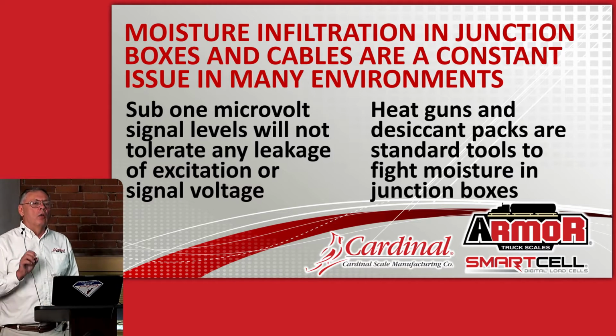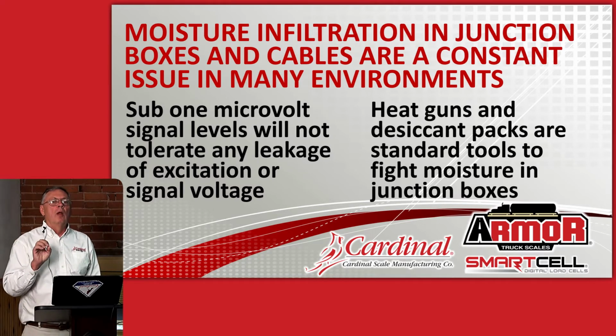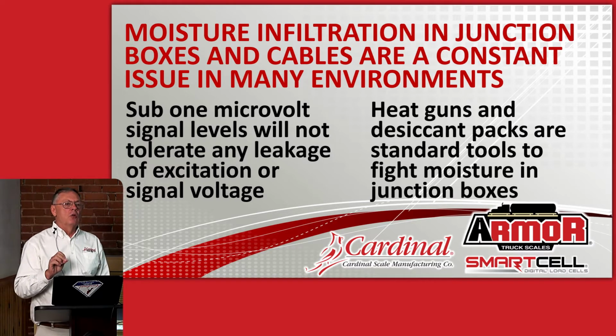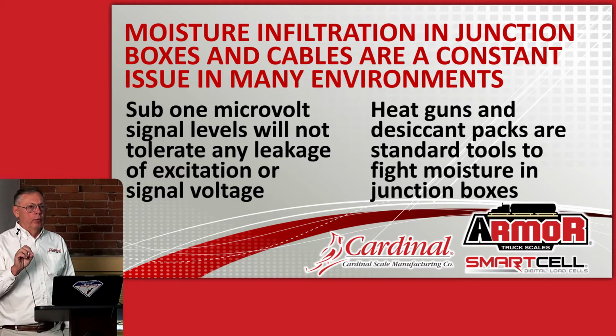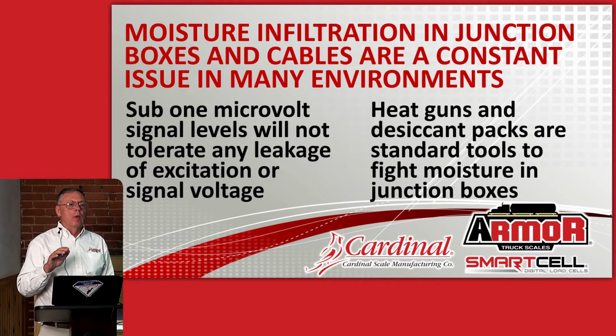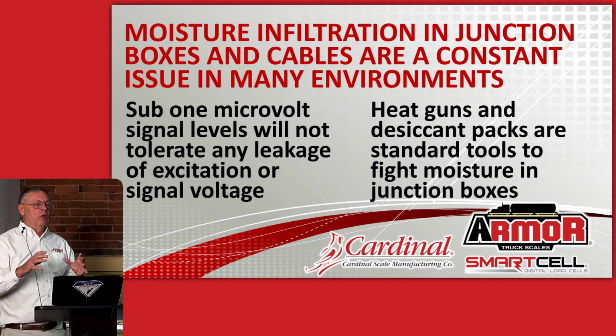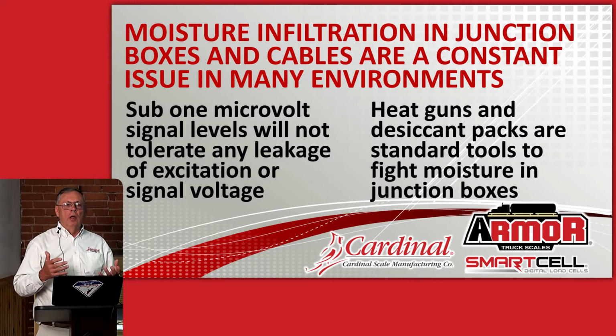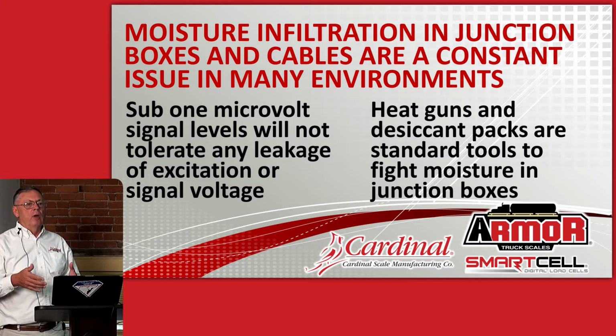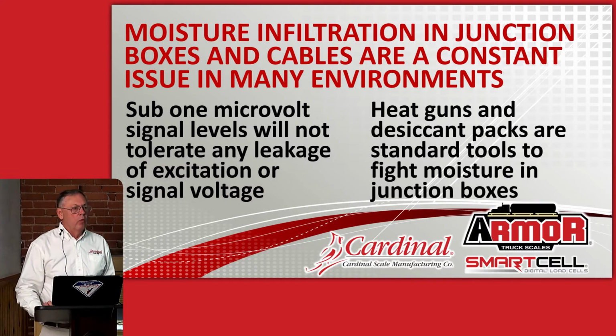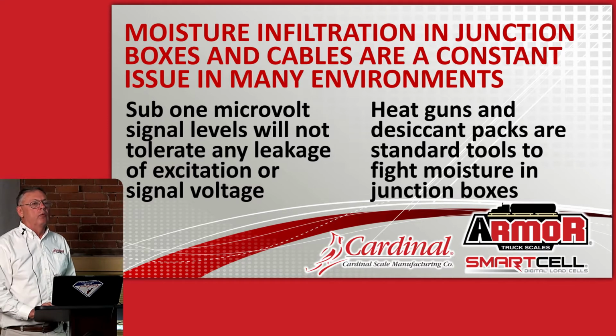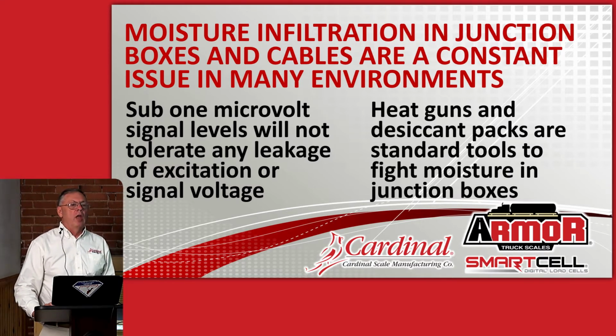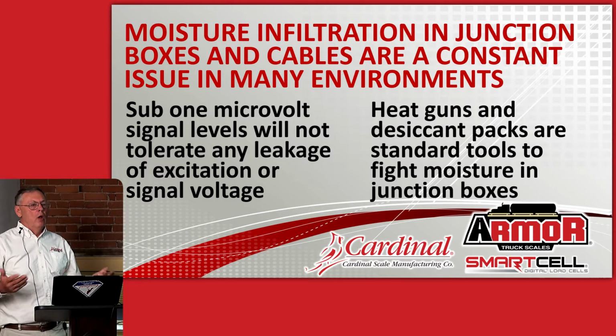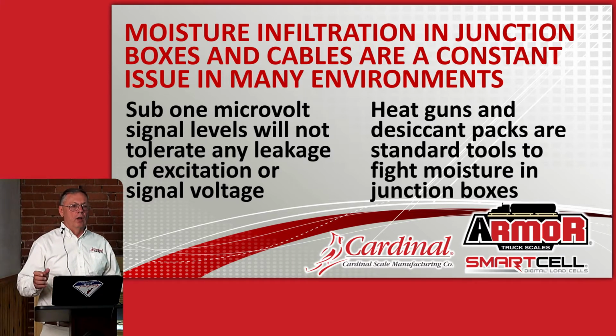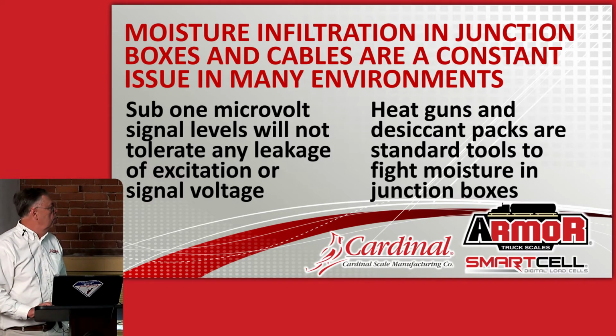On a typical truck scale, for a one division change, let's say we're going from a reading of 0 to a reading of 20 pounds, the amount of voltage that it takes to make that change is less than 1/2 millionth of a volt. So anytime we get any moisture, even a little bit of dampness or high humidity inside that junction box, you can get some voltage leakage and all of a sudden the scale doesn't run correctly. It may drift and you may get inaccurate readings. Over the years, scale technicians keep either a heat gun or a hair dryer in the cab of their test truck. Because the first thing you do if the scale's drifting, open up all the junction boxes and take a gun and try to get all the moisture out of it. That's just kind of a thing.